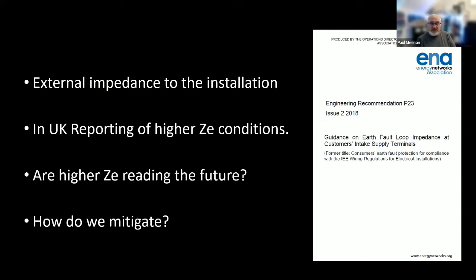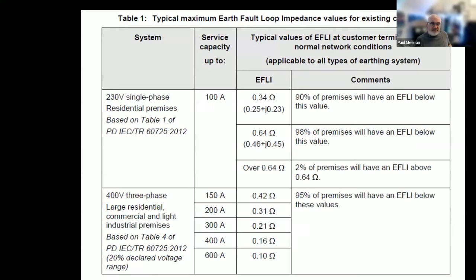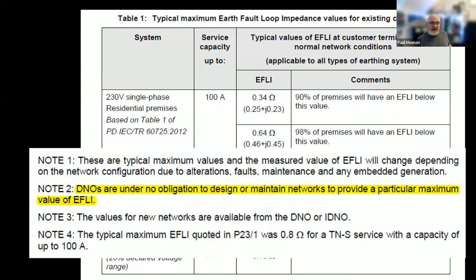Well, naturally, with age, if we're not maintaining stuff, then yes. So, how do we mitigate that? Well, you saw in the photos I was putting in discs or rods. There's some really good guidance out there as well, where, in England, we have a 100 amp service head, and it gives you the earth fault loop impedance. And it tells you that 90% will have below 0.34. But they also acknowledge there will be installations, millions of services, where they may be higher than that. And it's good that they're publishing this sort of stuff, because obviously we need to make sure we've got sufficient fault current to flow.